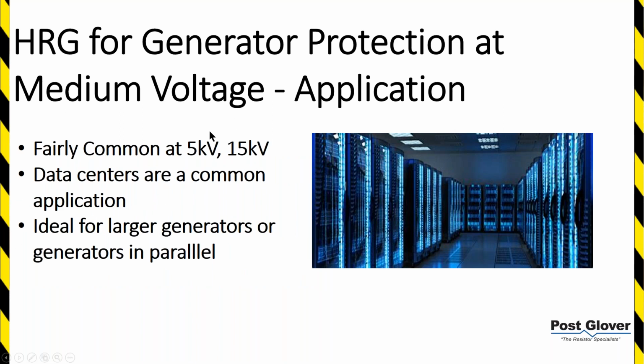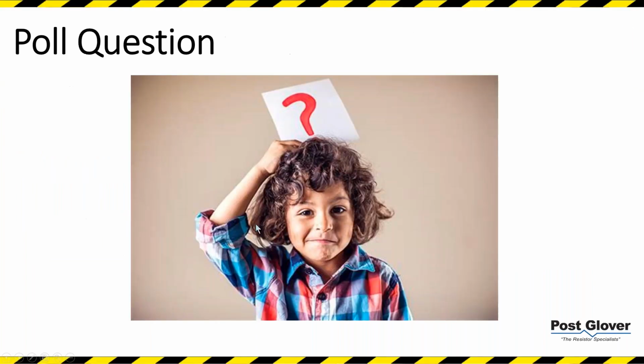It is fairly common at 5 kV, 15 kV. I see a lot of 15 kV, a lot of data centers at 15 kV. And we've done millions of dollars with this type of application for generator protection. Ideal for larger generators or generators in parallel, where you can get away with not using hybrid grounding because of the capacitive charging current.